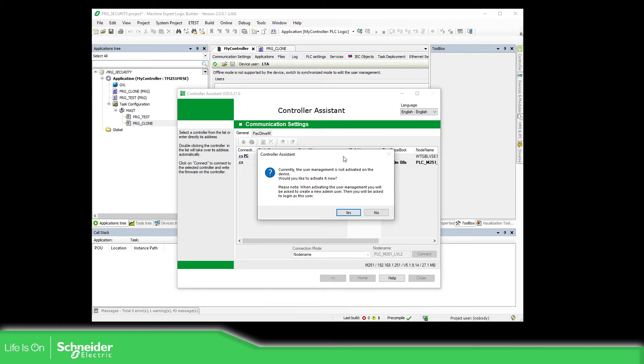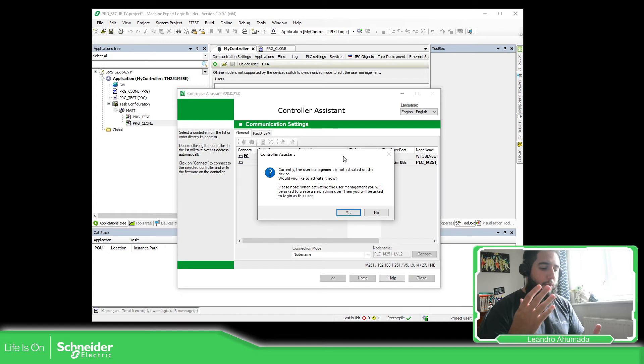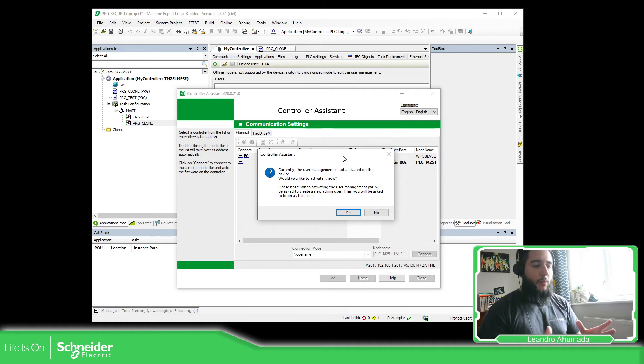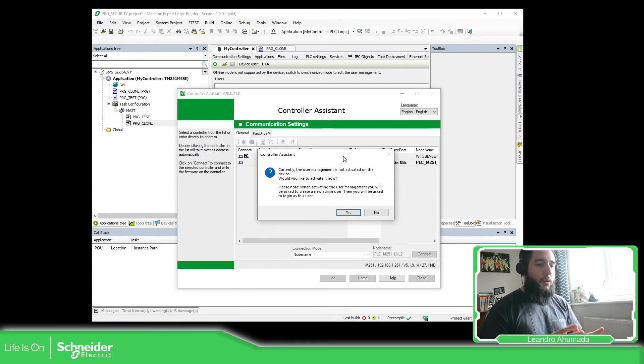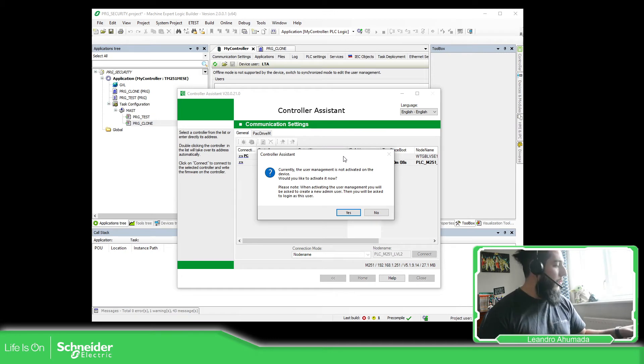Now this part is very important. In the new version of the firmware it's mandatory to create a user due to the California law, so the PLC will ask us to create a user before we can connect and download what we want to download. What I'm going to do is create just a temporary test user so we can proceed with the installation of our image with our own credentials.